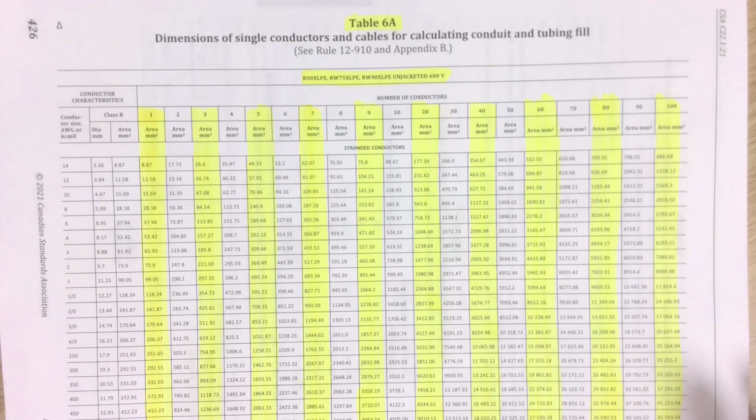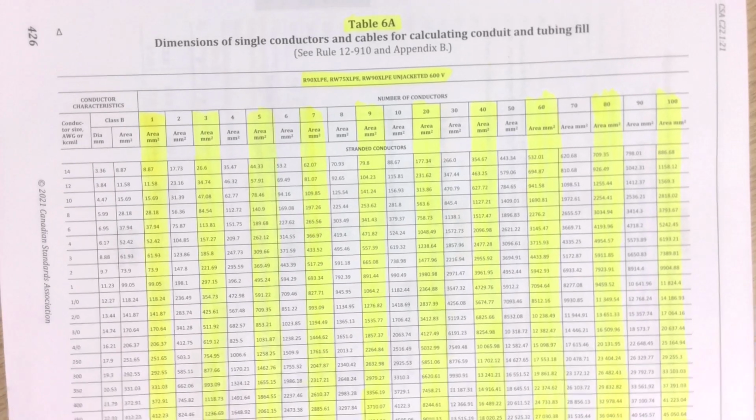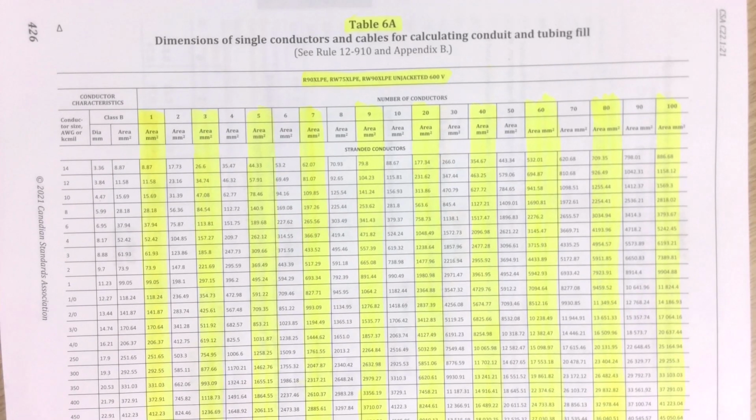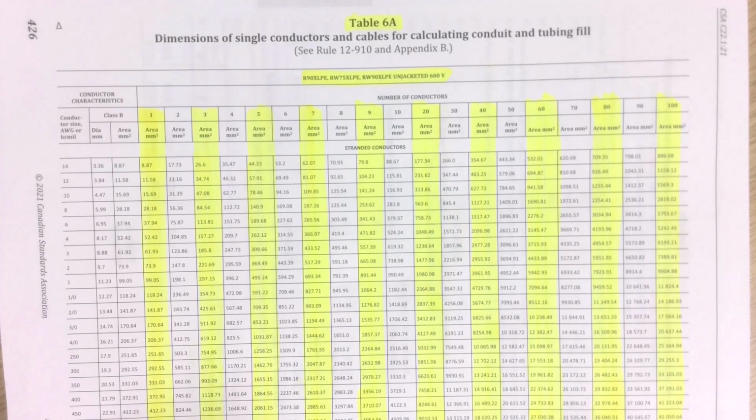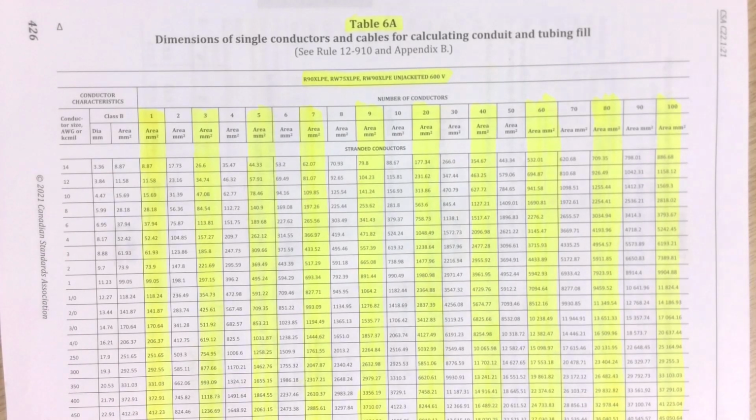And in general, in the field, since you want to leave room in your raceway for basically pulling in extra conductors after the fact, if you filled a conduit up as much as you could based on code, you would probably then upsize that conduit because you want to leave room for, one way you could call it, the oh shit factor, which is, oh shit, I forgot an extra wire.